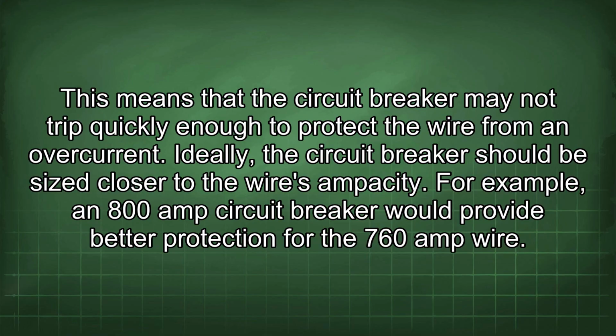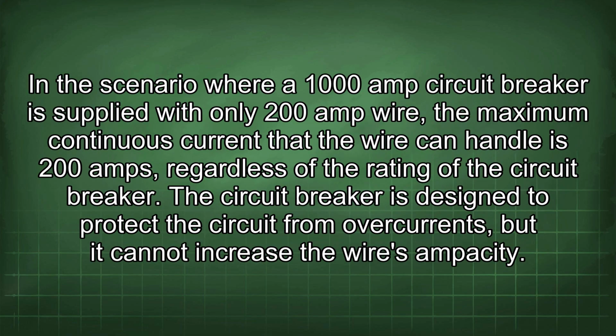Ideally, the circuit breaker should be sized closer to the wire's ampacity. For example, an 800 amp circuit breaker would provide better protection for the 760 amp wire. In a scenario where a 1000 amp circuit breaker is supplied with only 200 amp wire, the maximum continuous current that the wire can handle is 200 amps, regardless of the rating of the circuit breaker.